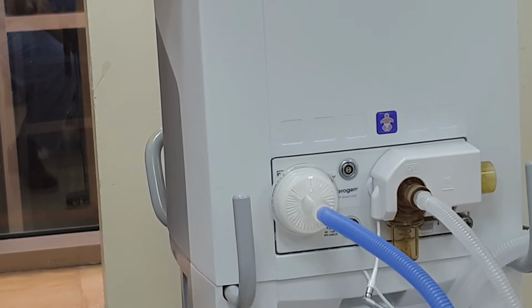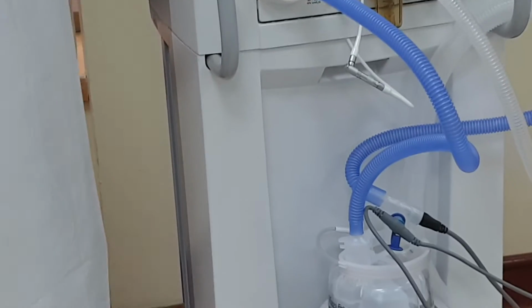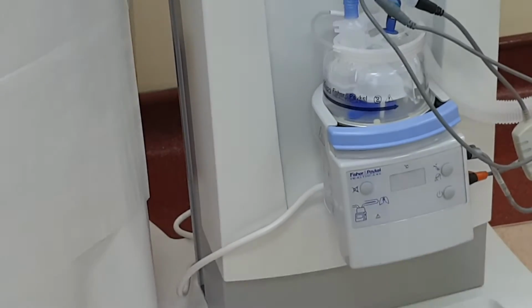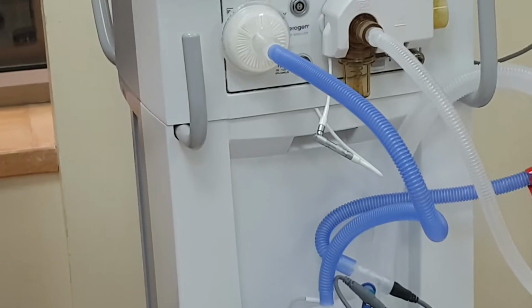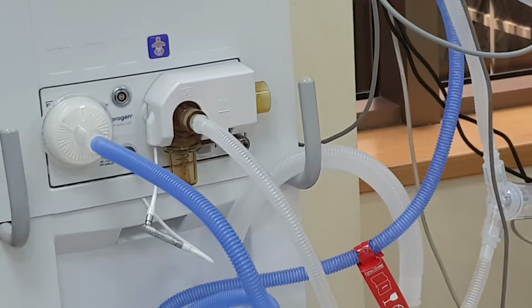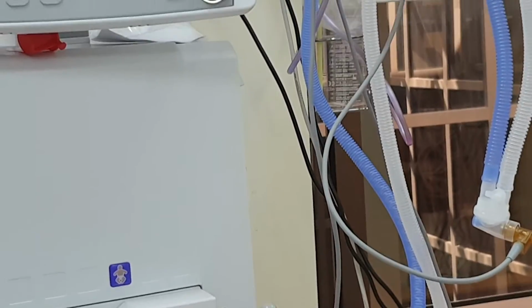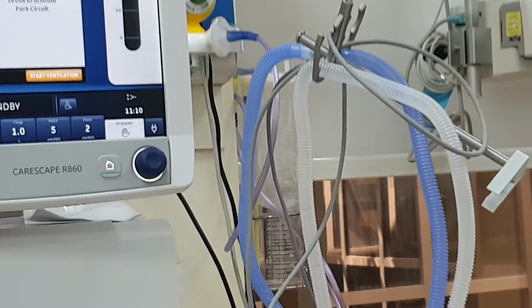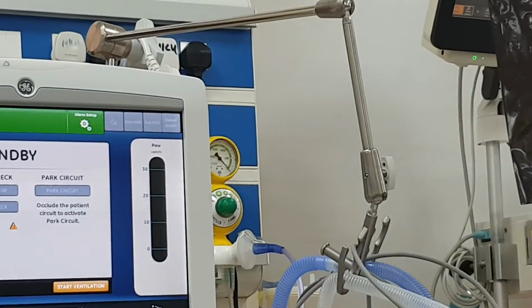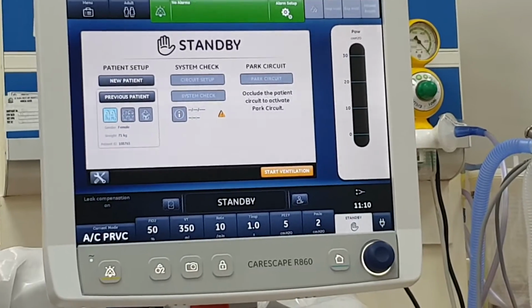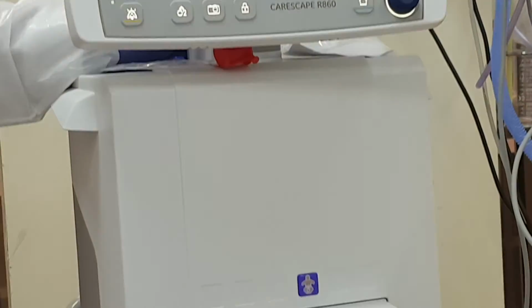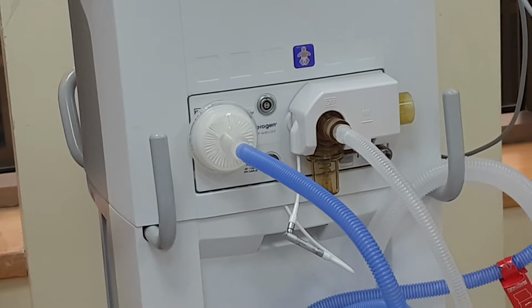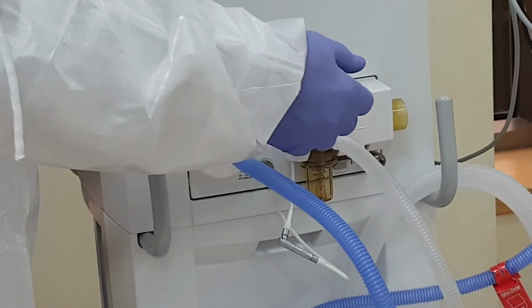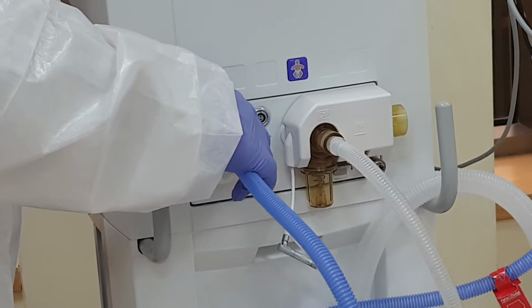When do we have to change it? You do have to change it if you have a failure in the closure of the swivel valve, which is basically the PEEP valve and the pressure control valve. So if you do have any risk of having open airway relief valve or sustained airway pressure, then this respiratory filter is replaced. After that, we could talk about the aerogen port.